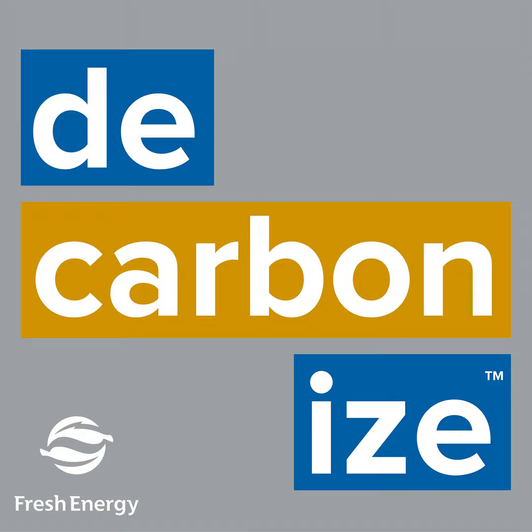Brian, to pick up on your point with different energy use profiles and interconnection of those types of buildings: the example I like is a hospital. A hospital has a very different energy use profile. Instead of requiring a lot of heat, they're actually dumping a lot of heat, doing a lot of cooling in the building, so they'd be dumping heat into an interconnected district system. If you interconnect residential buildings to that system, those buildings can use that waste heat from the hospital instead of using extra electricity to pump it up from the aquifer. That takes the COP value, the efficiency, and increases it exponentially. So it's a great way to make sure your district systems are operating at maximum efficiency.